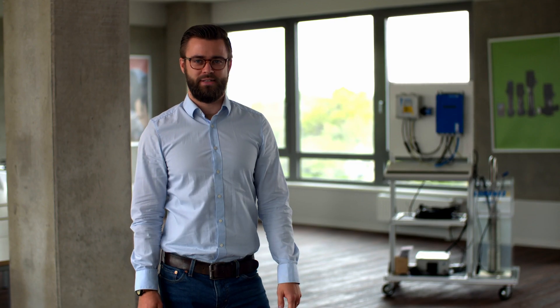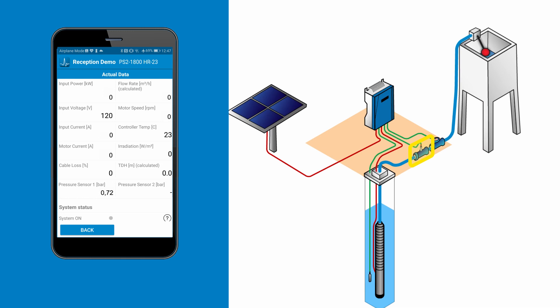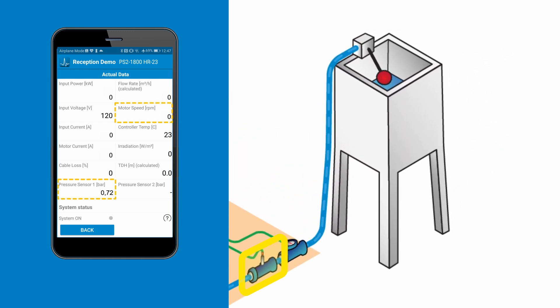Control by pressure is used most commonly in combination with float valves. As the valve closes, the pressure increases and the pump will stop. As the pressure reduces, the pump will start. By doing this we can manage the filling of remote tanks.